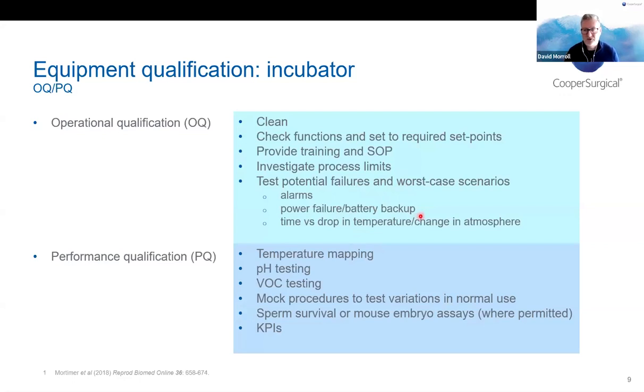So we will typically test, again in the example of an incubator, that alarms will sound if the door's left open, or if the temperature goes too high or too low, or the gas mix fails, or the CO2 level is too low. Where appropriate, we want to know what the effect is of a power failure. So how long will it maintain temperature and pH of our culture system if we have a total failure in mains power?